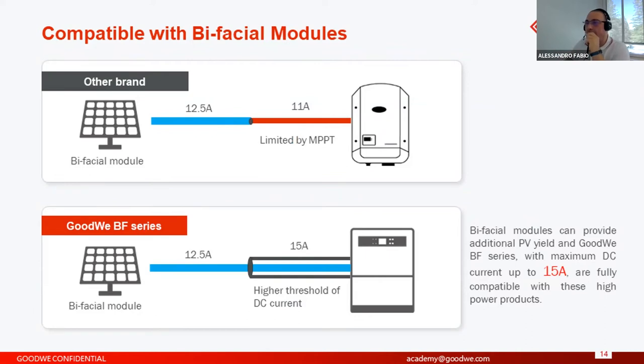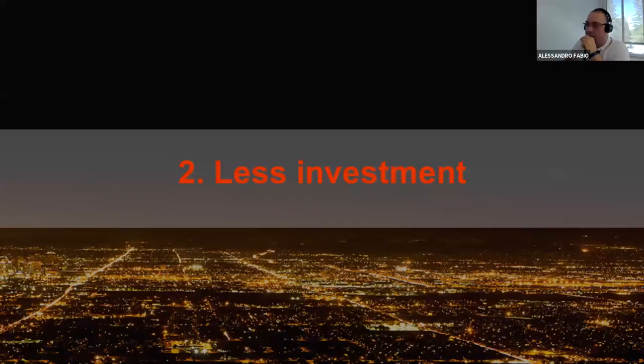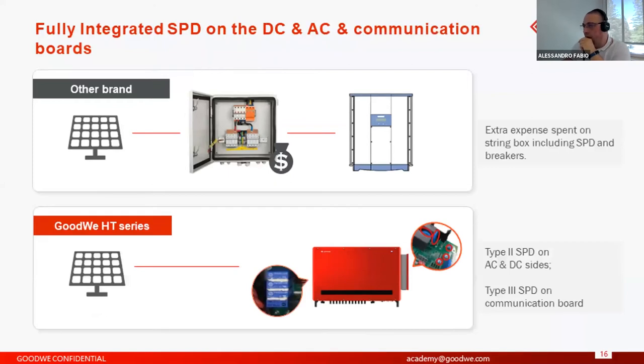So we spoke about the compatibility with bifacial modules. We have the possibility to use a special model, the BF series, where in our case we have 15 amps input for each string. So you have the possibility to use bifacial modules and to set up the PV plant in the right way. So, less investment.